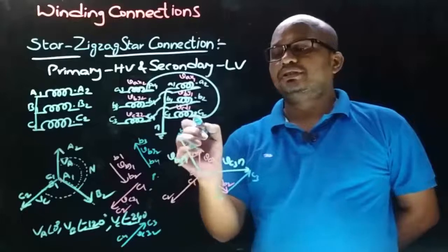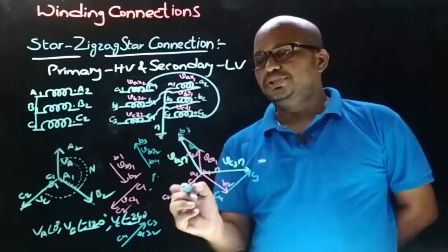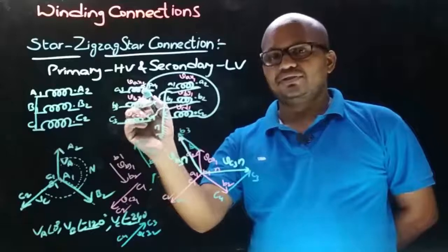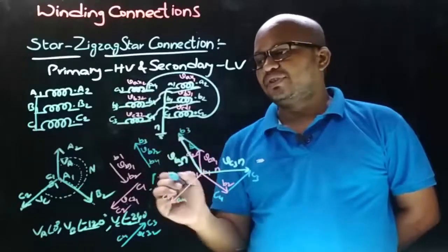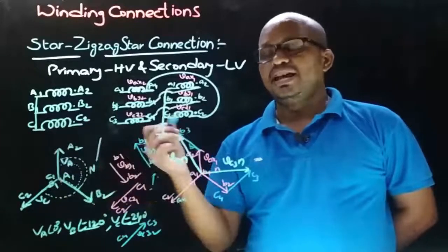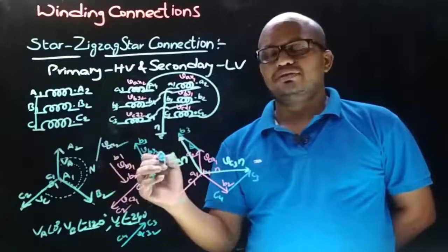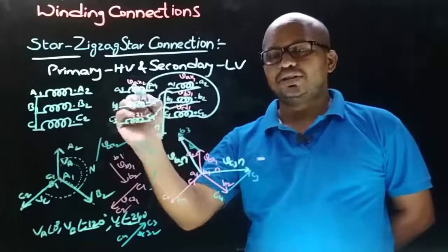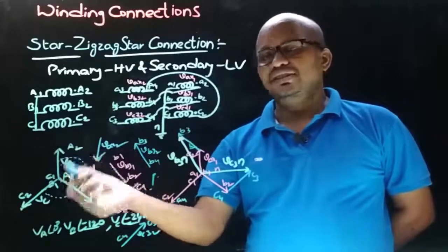Therefore, the resultant voltage is VC3N. Now observe that in winding connection, dot end C2 is having connection with A4, means to C2 there must be A4, means we must draw secondary side VAX2 phasor from C2. Therefore, let's draw secondary side VAX2 phasor somewhere here parallel to primary side VA phasor. Okay, and now we need to decide the direction of secondary side VAX2 phasor.